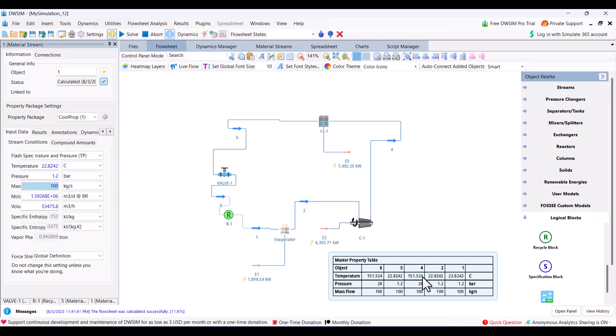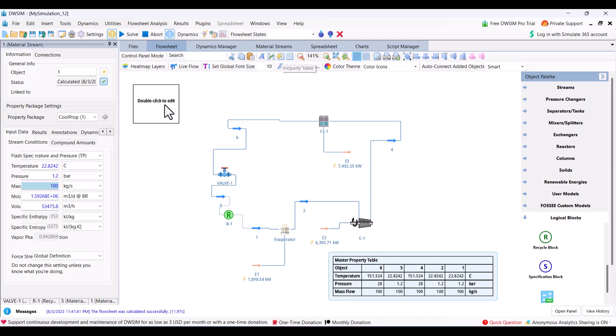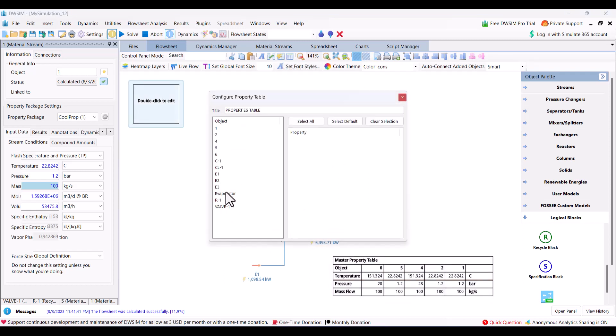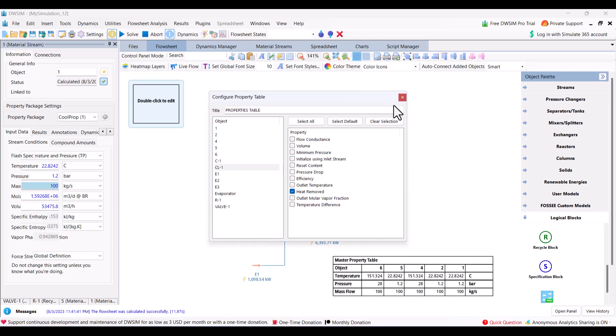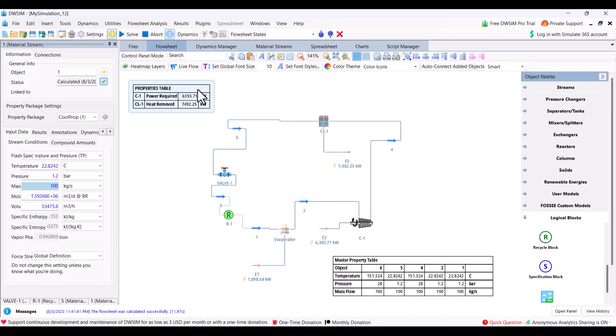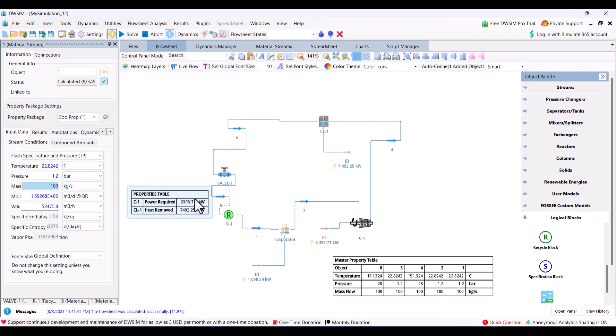After compressor at 4th stage, it is 150 degrees centigrade, and then after condensation it is in liquid stage. You can also add property table for condenser and compressor. Compressor power required and condenser heat removed. We can see power required for this heat pump is 6.3 or 6.4 megawatt and output is 7.5 megawatt. So if you want to calculate the coefficient of performance...